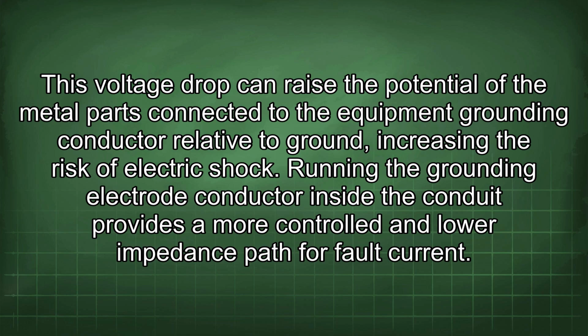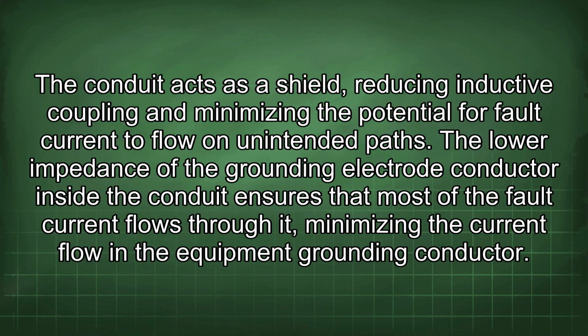Running the grounding electrode conductor inside the conduit provides a more controlled and lower impedance path for fault current. The conduit acts as a shield, reducing inductive coupling and minimizing the potential for fault current to flow on unintended paths. The lower impedance of the grounding electrode conductor inside the conduit ensures that most of the fault current flows through it, minimizing the current flow in the equipment grounding conductor.